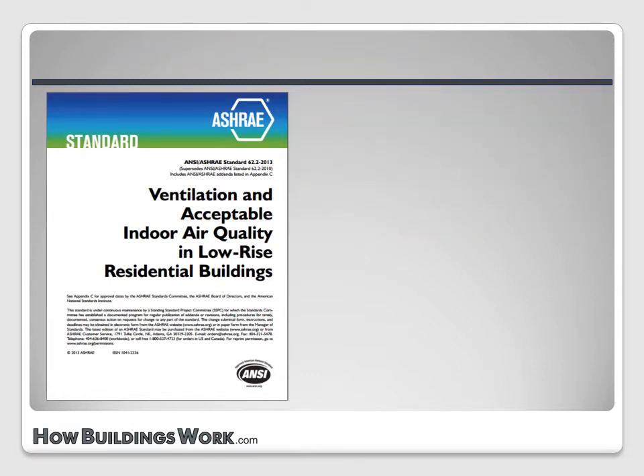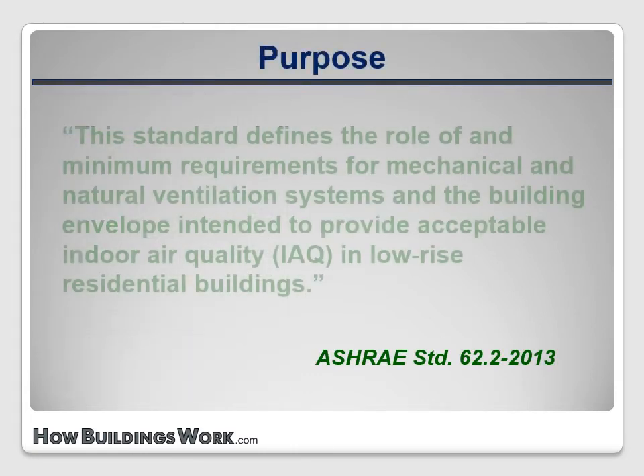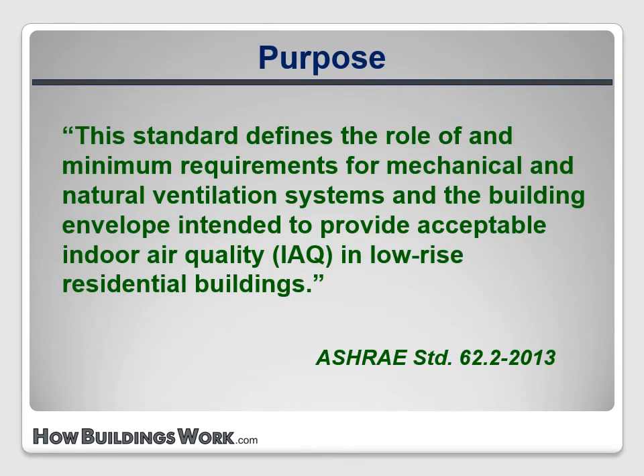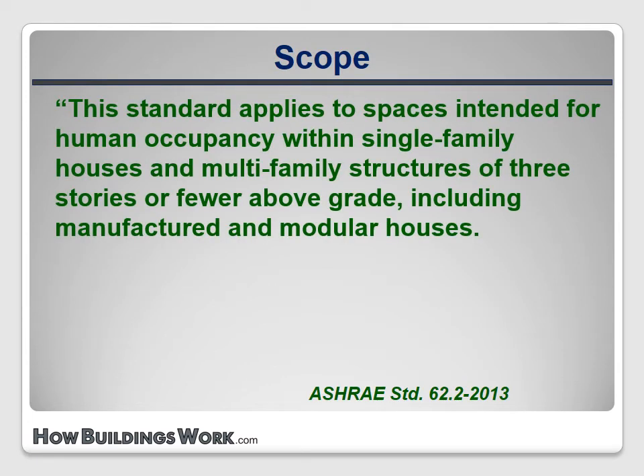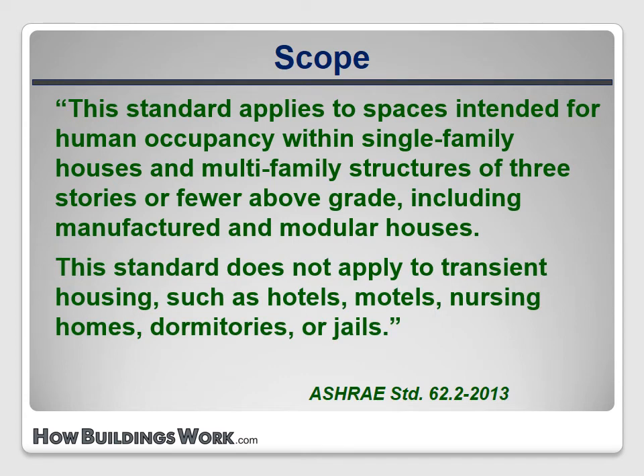Here are some quotes directly from the 2013 version of Standard 62.2. The purpose states that this standard defines the role of and minimum requirements for mechanical and natural ventilation systems and the building envelope intended to provide acceptable indoor air quality (IAQ) in low-rise residential buildings. The scope states that this standard applies to spaces intended for human occupancy within single-family houses and multi-family structures of three stories or fewer above grade, including manufactured and modular houses. This standard does not apply to transient housing such as hotels, motels, nursing homes, dormitories, or jails.